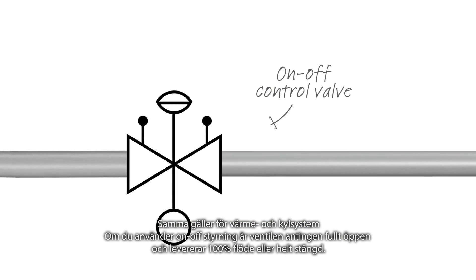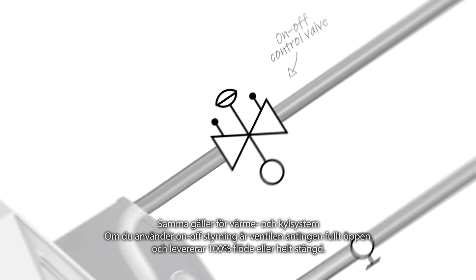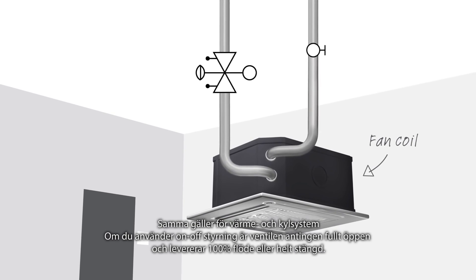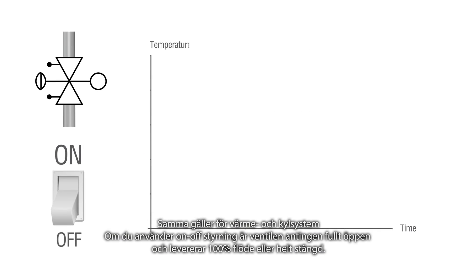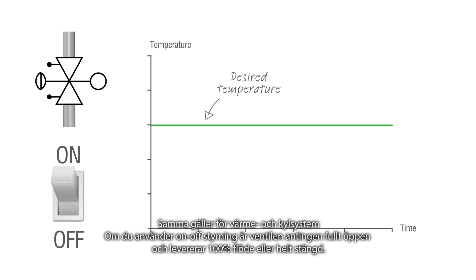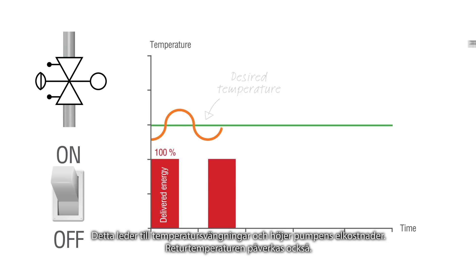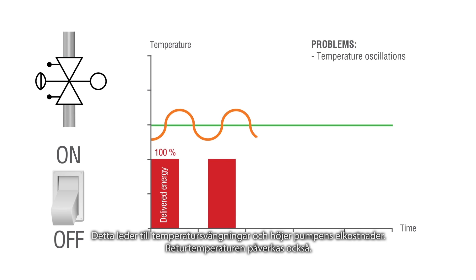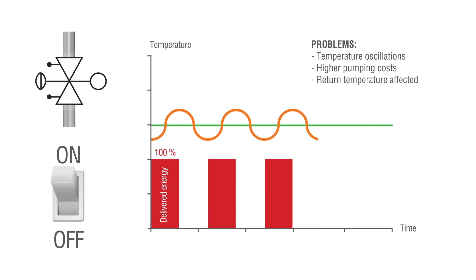Similarly in heating and cooling systems, if you use on-off control the valve is either fully open and delivers 100% flow or fully shut. This leads to temperature oscillations and higher pumping costs, and the return temperature is also affected.